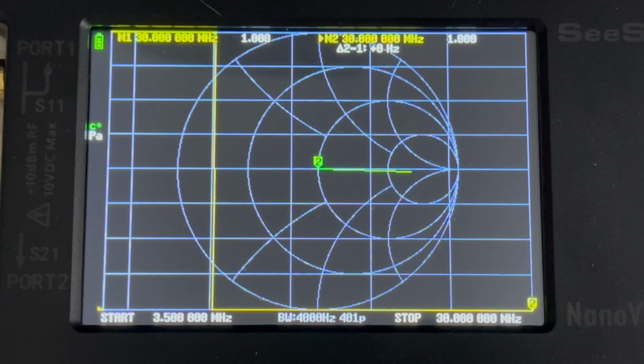The very basic measurement sequence would be to go to stimulus, go to start, stop, and perform your calibration. Then you want to save it. And then you connect the device under test. If you see the letters DUT, Delta Uniform Tango, they're referring to device under test.